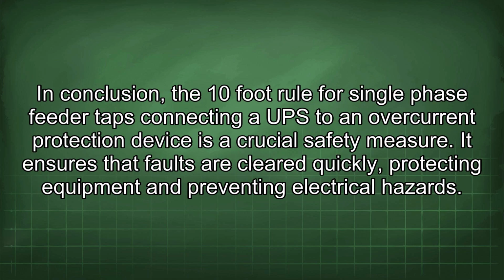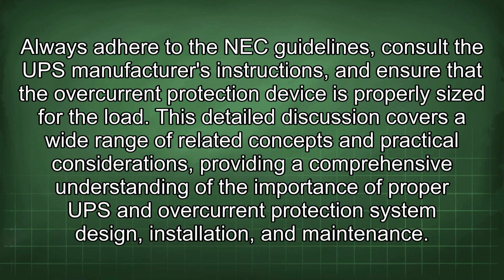In conclusion, the 10-foot rule for single-phase feeder taps connecting a UPS to an overcurrent protection device is a crucial safety measure. It ensures that faults are cleared quickly, protecting equipment and preventing electrical hazards. Always adhere to the NEC guidelines, consult the UPS manufacturer's instructions, and ensure that the overcurrent protection device is properly sized for the load. This detailed discussion covers a wide range of related concepts and practical considerations, providing a comprehensive understanding of the importance of proper UPS and overcurrent protection system design, installation, and maintenance.